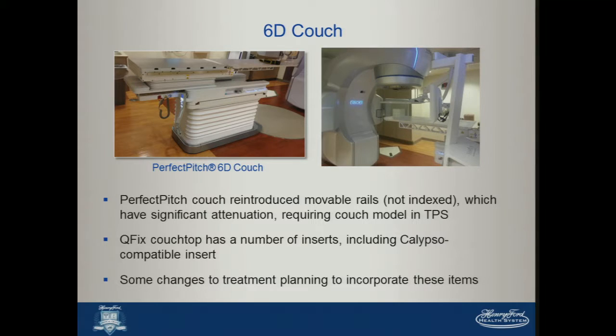So the Perfect Pitch 6D couch is shown here. Just a few points about that. The Perfect Pitch couch reintroduced movable rails, which are not indexed, which have significant attenuation, requiring a couch model in the treatment planning system. That couch model is available as a standard feature in ARIA version 13, but not earlier versions, so we built our own in that case. So that's something you want to take into account.